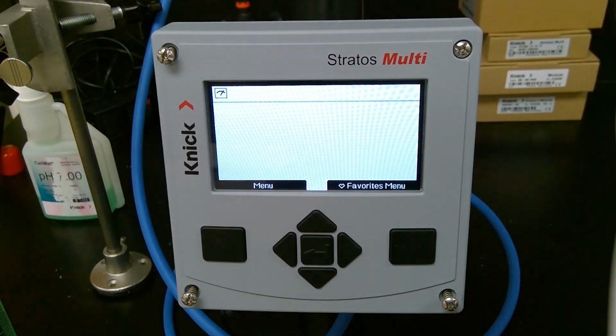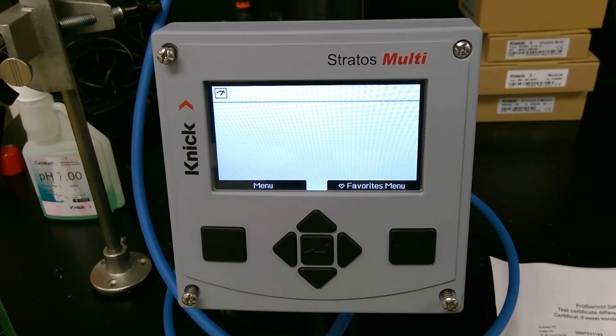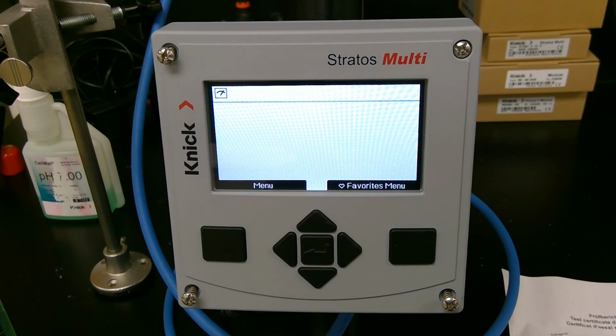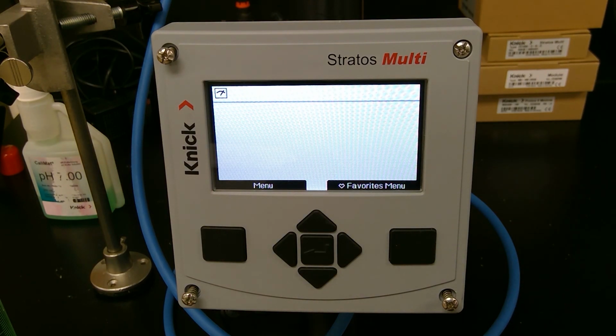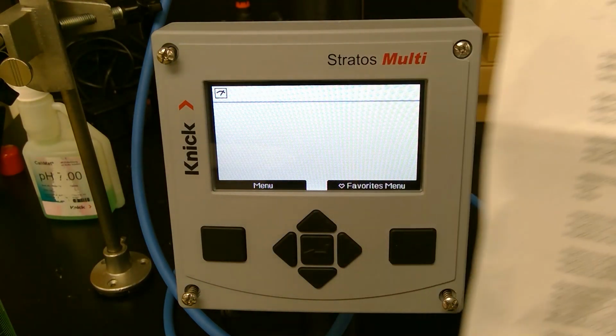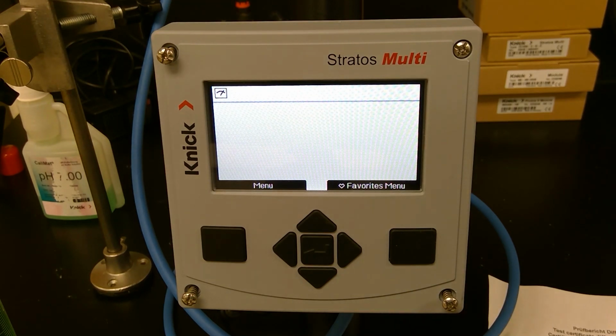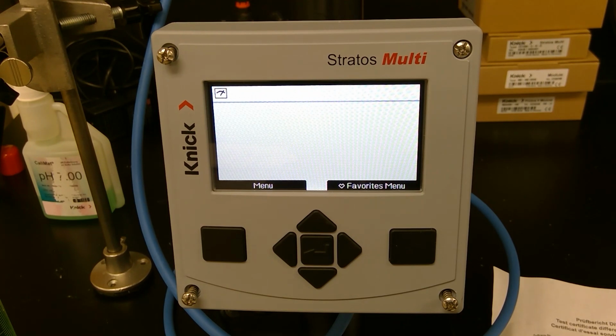Now you're going to need, as I mentioned before, the test certificate with the sensor that you have ordered. So the customer needs to make sure when they open the box, this will be in a clear plastic protective sleeve. They need to make sure they have this because there's information on here that we need to take and put into the multi to make the Type 18 function correctly.